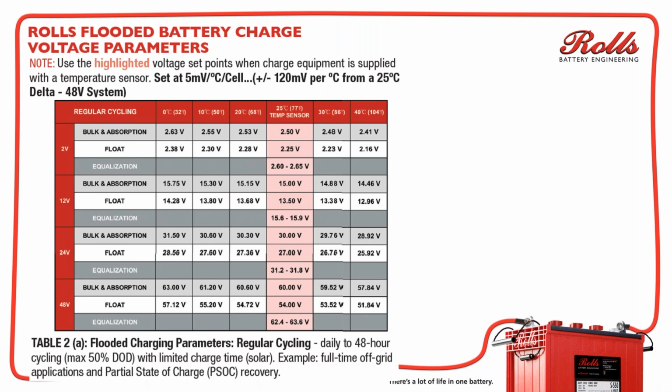What that means is we want to know what the actual battery temperature is, not the ambient temperature of the battery bank. So if you're in BC and your ambient temperature is 18 degrees Celsius, a lot of installers will tell you, oh yeah, you're in BC, it only gets to 25 degrees C here, max, so you don't need a battery temp sensor. Well, that is 100% false, okay?